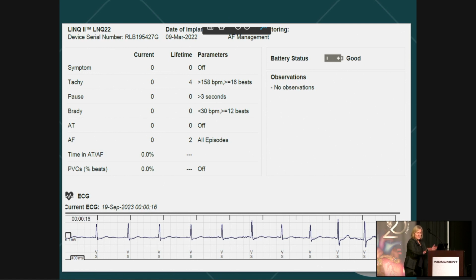Like if a patient is having symptoms that aren't being recorded, you can decrease the trigger rate from like 158 to 140. Or the pauses, you probably don't want to change that. But for brady events, if they're having symptomatic bradycardia with rates in the 40s, you're not going to see it with the setting programmed to less than 30, unless they start having pauses or more significant bradycardia.